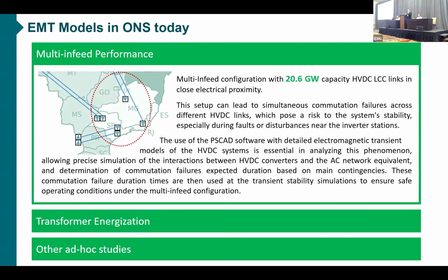For multi-feed performance, we have a multi-feed configuration with a little over 20 gigawatt capacity. The HVDC LCC links are in close electrical proximity, and they all converge towards the southeast region of Brazil, our main load center. We know this setup can lead to simultaneous commutation failures across different HVDC links, which poses a risk to system stability, especially during faults or disturbances near the inverter station. So nowadays we use PSCAD with detailed EMT models of these HVDC systems to analyze this multi-feed phenomena and simulate the interaction between the converters and the AC network to determine the commutation failure times.